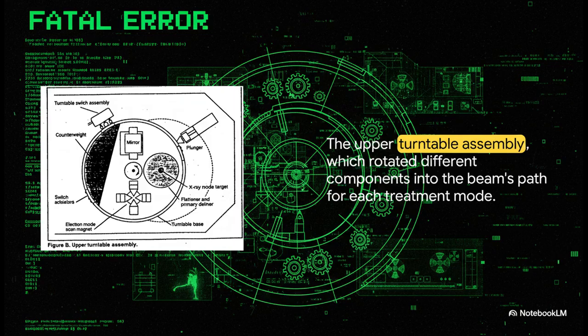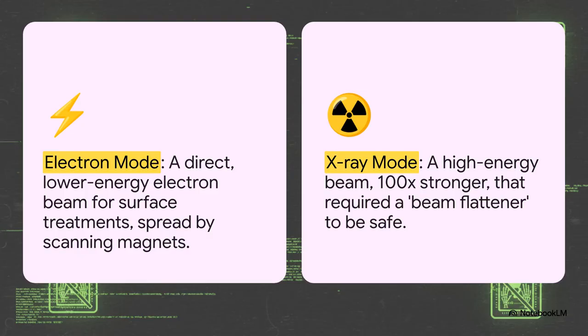At the physical heart of this machine was this component you see here, the turntable. Its whole job was to rotate different parts into the path of an electron beam, and that's how it switched between two very different modes of treatment. So the machine basically had two main settings. First was a low-power electron mode. This sent a beam of electrons directly to treat tumors right on the surface. Simple enough. But the second was a high-power X-ray mode. And in this mode, the electron beam was about 100 times more intense. It would hit a metal target to create powerful X-rays that could get to deeper tumors.